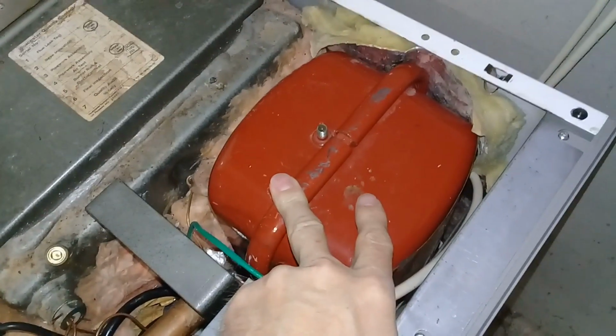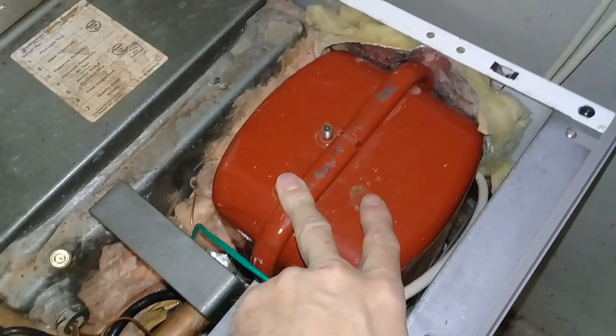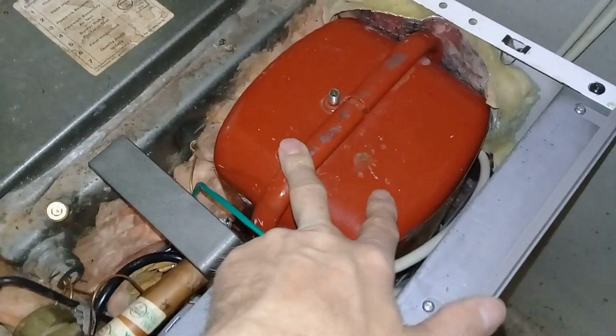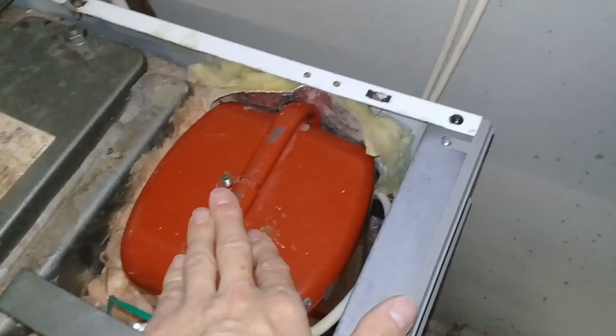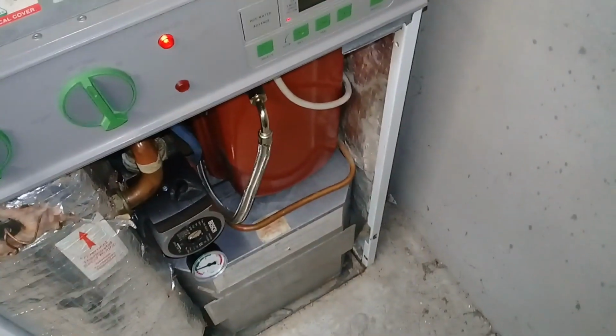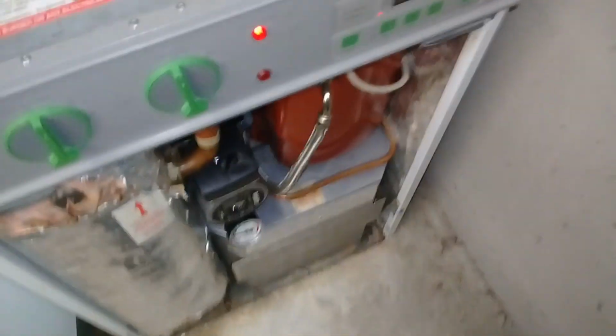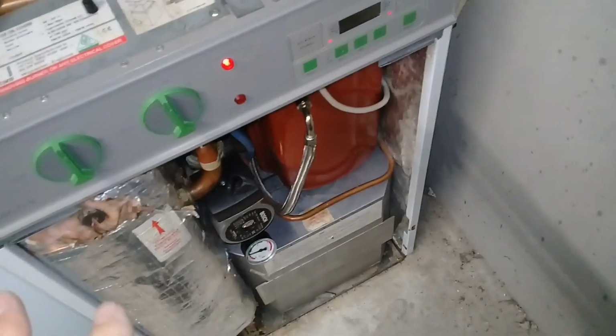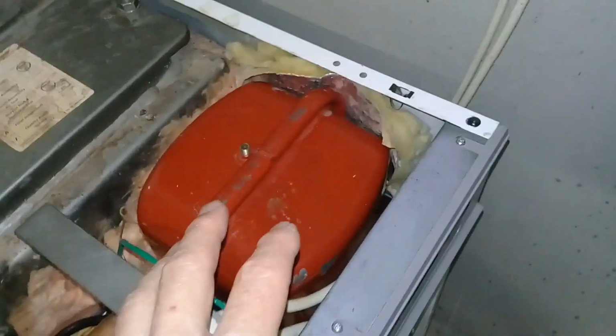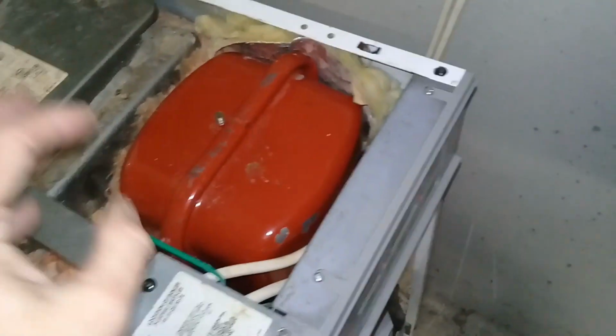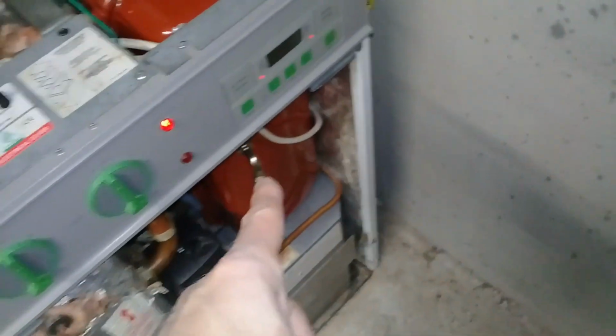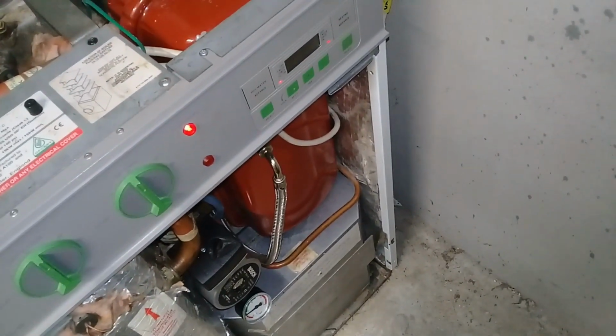At the time of making this video, I bought it from Plumarina, £89. That's quite a good price. It's quite hard to find anyone else doing them at a cheaper price. This one I think is probably about 12 years old. So what I'm going to do probably is, once the new one arrives, drain the system again, make sure there's no pressure in it, which there won't be. Take the pipe off, remove this one. The new one comes with nitrogen and it should be 1 bar, but I checked with a pressure gauge.